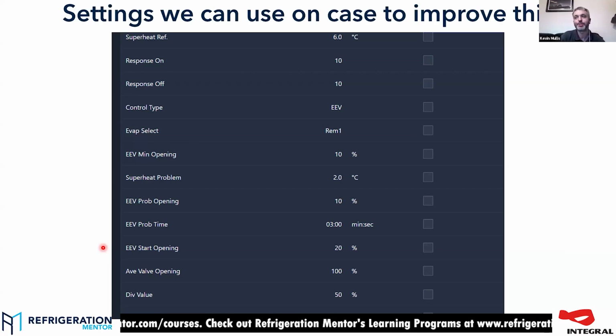Start opening gives you the opportunity to get liquid to your probe if you're running on a probe for inlet temperature rather than a transducer. You can set that to 10% with a transducer because it will see the true superheat from the get-go. If you've got an inlet probe as your only source of your evaporating temperature, especially if it's a long way away from the inlet, you need that number to be a little bit higher to get some liquid to it.